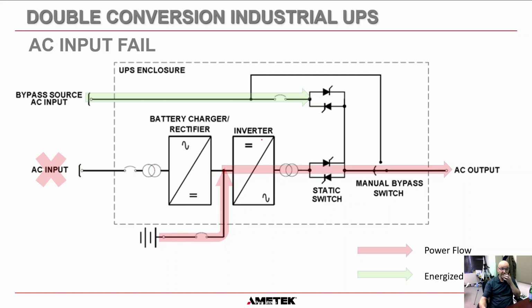Now, if we have a power failure, an AC input failure, we can see here we've lost our AC input, then the batteries take over. We do not switch to battery. The batteries are in parallel with the charger. So when we lose power to the charger, the batteries just continue to supply the DC to the inverter.